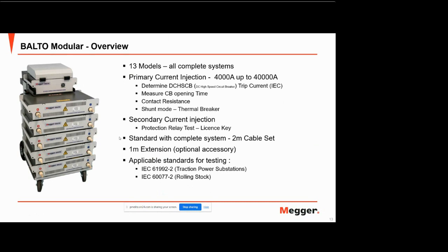The first one and the most important one is to actually do the trip current test. So it determines the DC high-speed circuit breaker trip current. The second one that it does, it actually measures the circuit breaker opening time. So you can see how quickly your DC high-speed circuit breaker opens. And also we measure the contact resistance. So these are some of the main tests that are also specified in the IEC 61992 and IEC 60077. We also have a shunt mode. So if you have a thermal breaker or a molded case circuit breaker that has a thermal trip, you can apply the shunt mode, which is a constant current test that can also output high current over a longer period of time to test the thermal trip on a molded case circuit breaker.